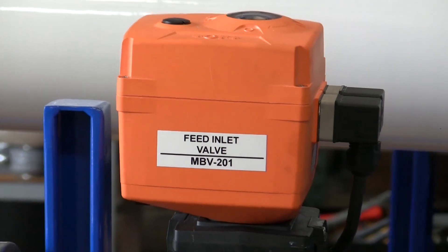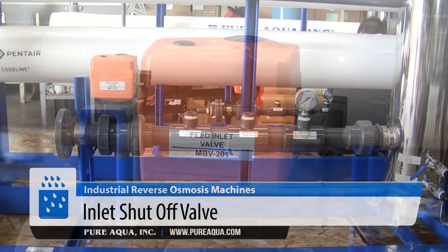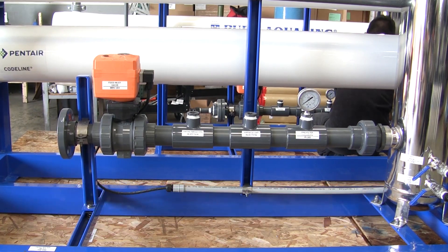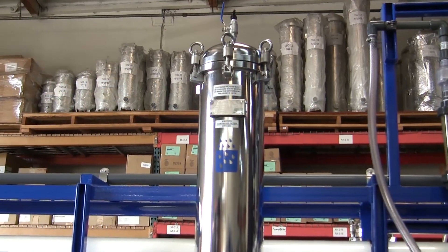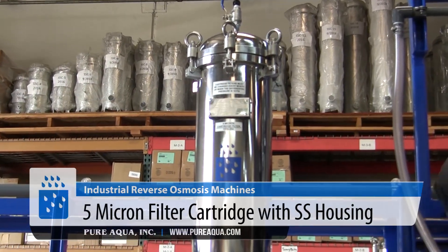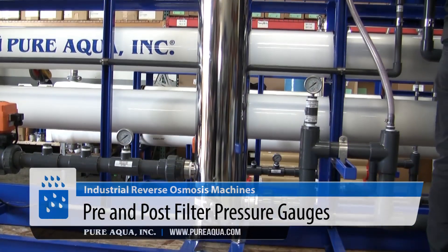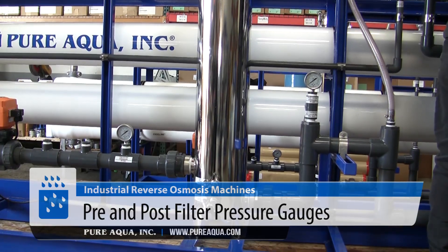The filtered water is fed through the inlet shut off valve, and then it's going to be dosed with dechlorination chemicals and antiscalant, then filtered down to a polisher of 5 micron. We can see the gauges before and after to monitor the differential pressure between the inlet and outlet of the filter.